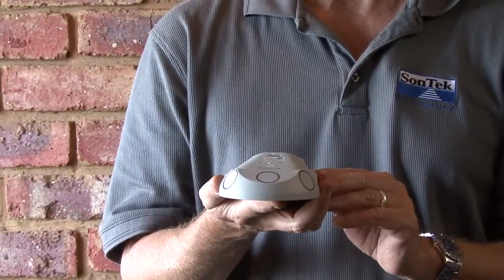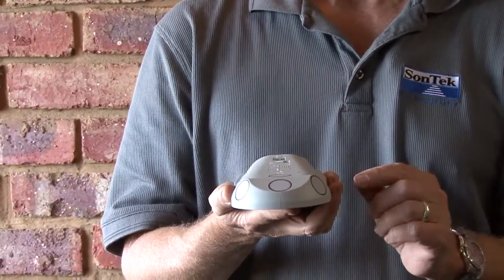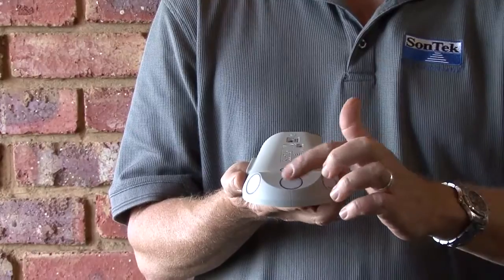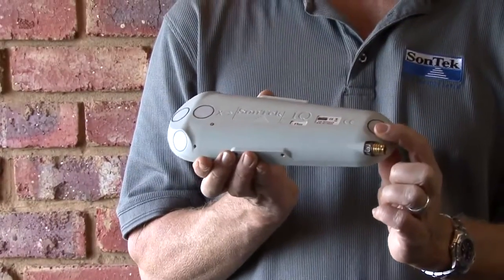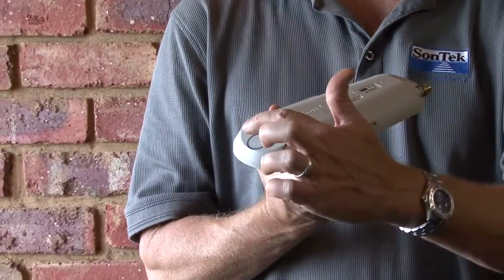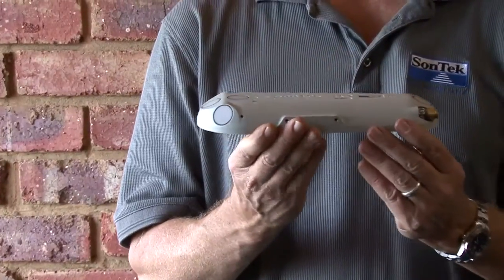We actually use acoustics to measure velocity and water level. These are acoustic transducers. They have a 3 megahertz frequency, and these outside beams here are what we use to scan the velocities in the channel.